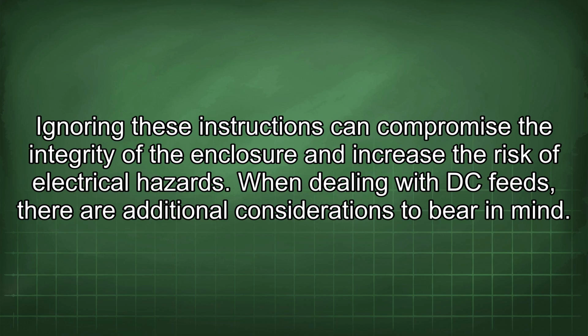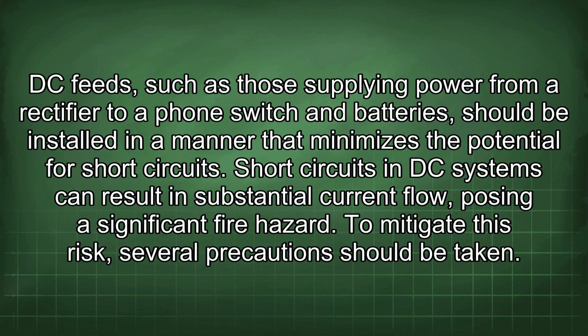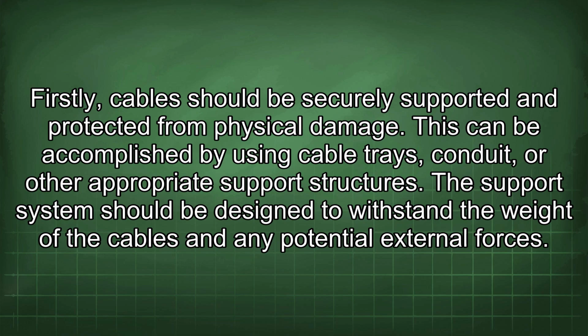When dealing with DC feeds, there are additional considerations to bear in mind. DC feeds, such as those supplying power from a rectifier to a phone switch and batteries, should be installed in a manner that minimizes the potential for short circuits. Short circuits in DC systems can result in substantial current flow, posing a significant fire hazard. To mitigate this risk, several precautions should be taken. Firstly, cables should be securely supported and protected from physical damage. This can be accomplished by using cable trays, conduit, or other appropriate support structures. The support system should be designed to withstand the weight of the cables and any potential external forces.